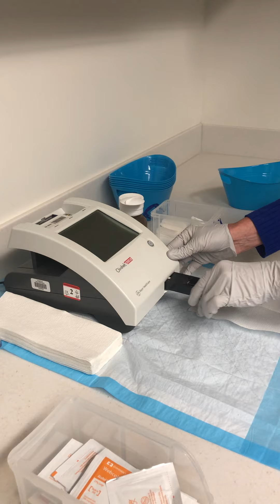Weekly, what we want to do is pull the test table out of the machine, and you'll see that there's two pieces here, okay? You never want to touch this white bar here. This is the calibration bar. This should never get dirty. If it is dirty, then there are special instructions in the manual on how to clean it, but we want to avoid touching this or getting it wet.